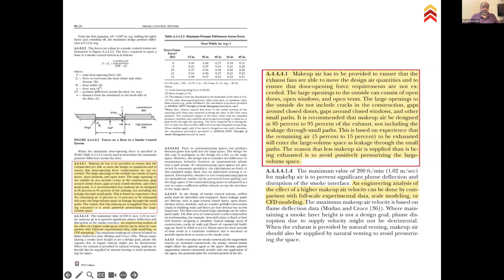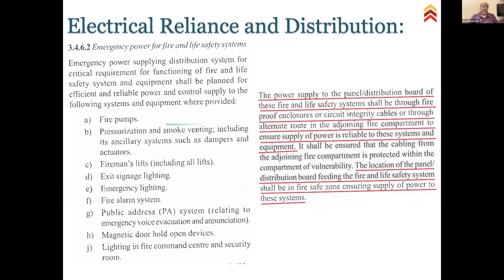Electrical resilience for the fire and smoke system is very, very important. We referred to NFPA 110, towards EPS, Emergency Power Supply Systems, and picked up some of the most important areas which must function during fire. During fire your STP can stop, your chiller can stop, many things can stop, but identified equipment must function during the fire scenario, and their connectivity and systems have to be highly reliable to ensure your pressurization fans or smoke management fans, in my version after the extinguishment of fire, are able to perform despite electricity not being provided to other non-important areas.